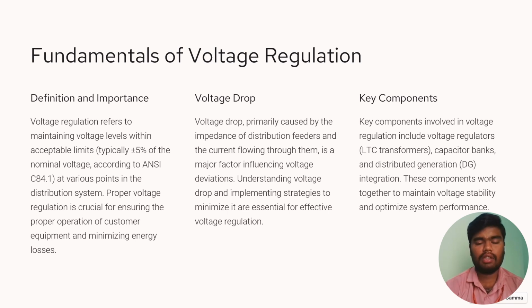The second one is voltage drop. Voltage drop, primarily caused by the impedance of distribution feeders and the current flowing through them, is a major factor influencing voltage deviations. Understanding voltage drop and implementing strategies to minimize it are essential for effective voltage regulation.